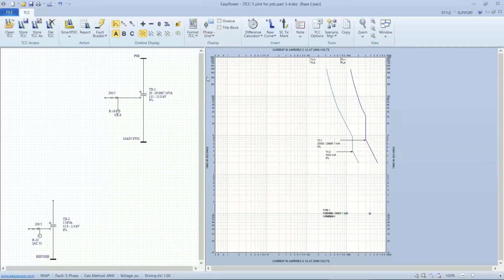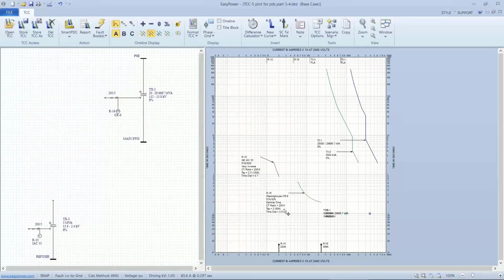Now, the thing that's tricky is that normally you're looking at your phase overcurrent. We just want to look at the ground plot. So we need to apply a line to ground fault. And by doing that, now we see those curves set up for each of those devices. It's significant because R16 is set up with a 400 amp curve, a 400 amp limit resistor, and we've scaled the curve to have a decreasing trip time with an increasing current. So the way it's currently set up, the higher the current, the faster the trip. So this would survive a lower current for a longer amount of time.